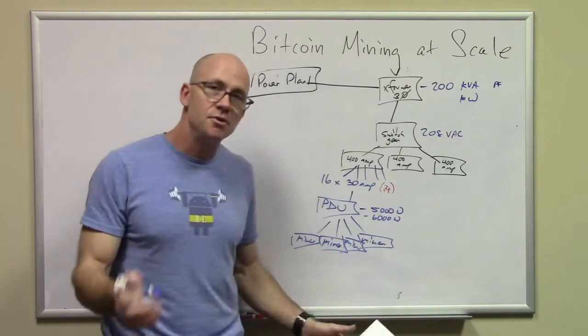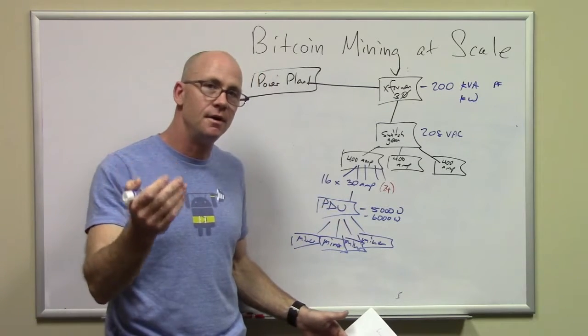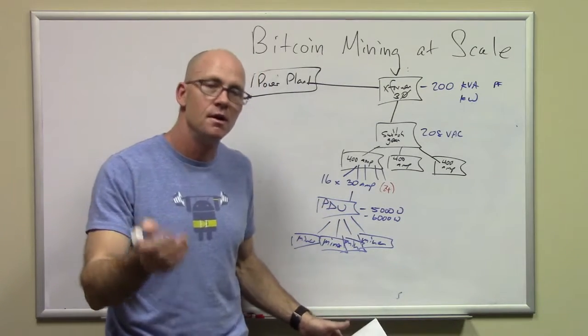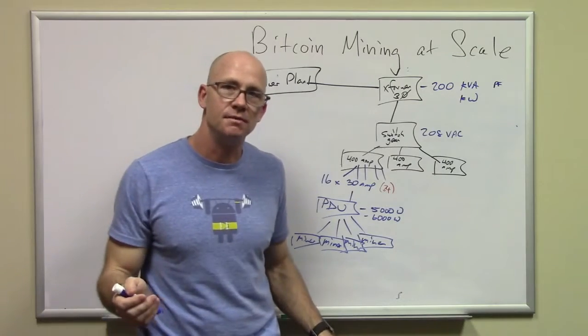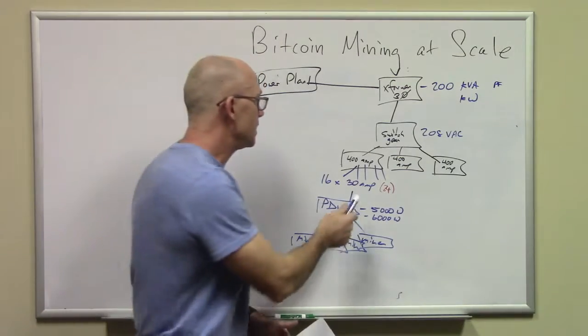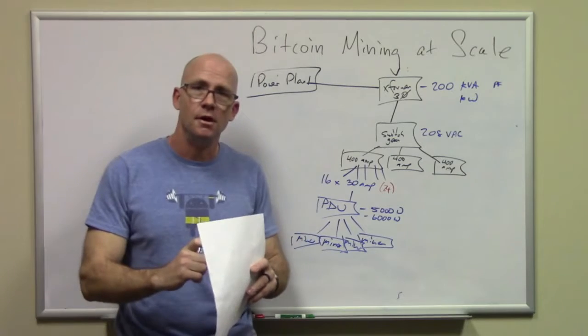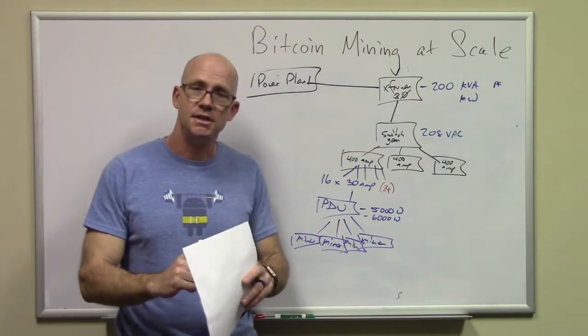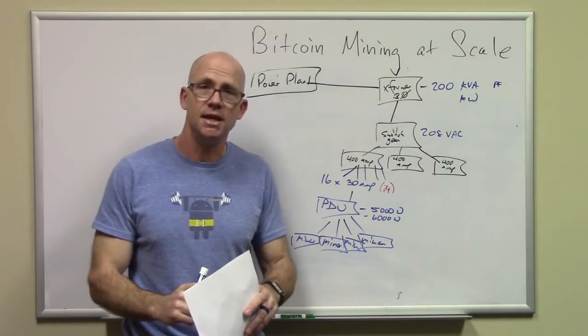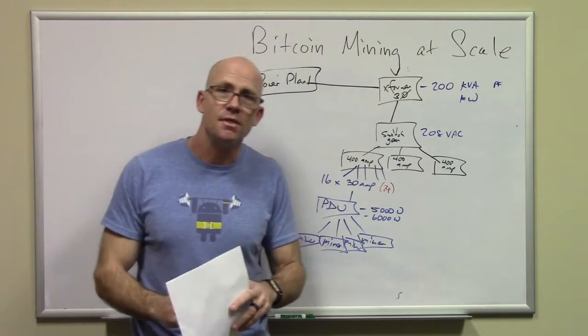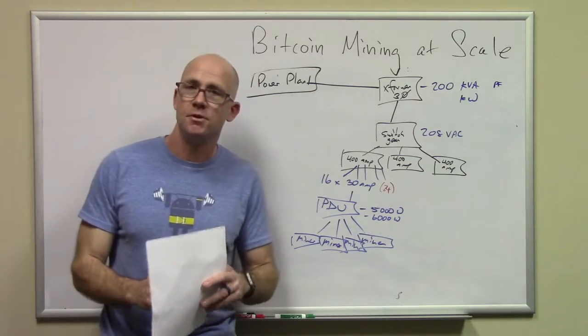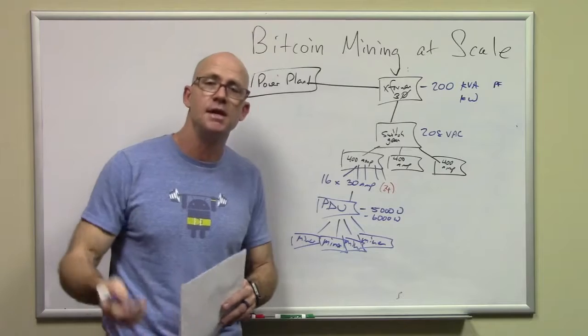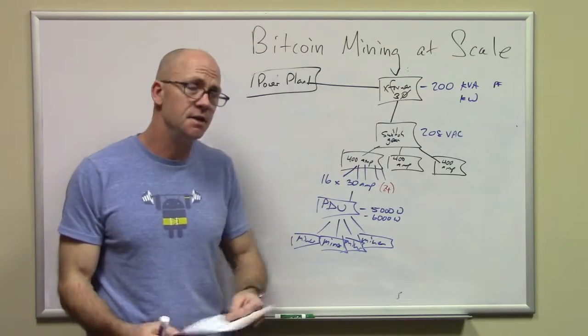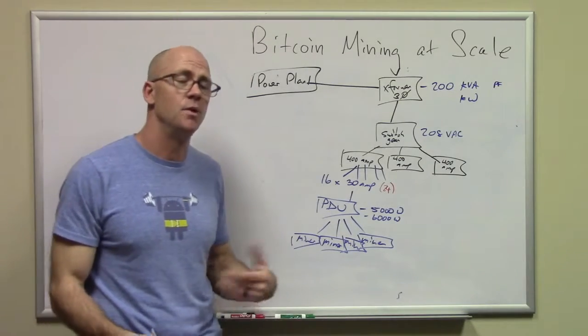Anyway, whenever an electrician talks about a panel or a breaker, automatically think 80% of that. Because if they say it's a 30 amp receptacle, that means 24 amps steady state load, and we're doing things at steady state load. If you try to run 30 amps through a 30 amp receptacle 24 hours a day, it'll probably overheat and pop. In the least case, it'll be less efficient just because the electrical wiring warms up.